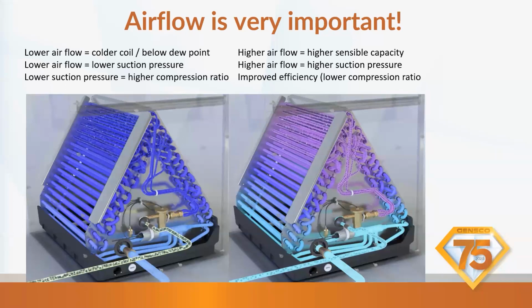So lower airflow, on this is one of the coils in there, right? So lower airflow could mean a colder coil below dew point. Lower airflow, lower suction pressure. Lower suction pressure equals higher compression ratio, right? Higher airflow, higher sensible capacity. Higher airflow equals higher suction pressure. And then higher airflow also improves the efficiency and lowers the compression ratio. So there's a deeper dive into that improved efficiency too. But you could just see how the airflow affects refrigerant, right?